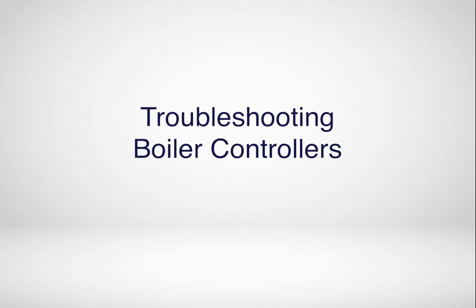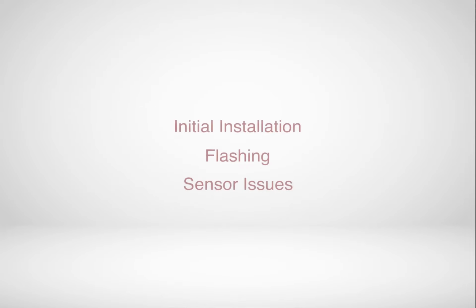When boiler systems do not read correctly, it generally falls into one of three categories. The initial installation was not done correctly, there is flashing at the sensor, or it is time to clean, calibrate, or replace the sensor.